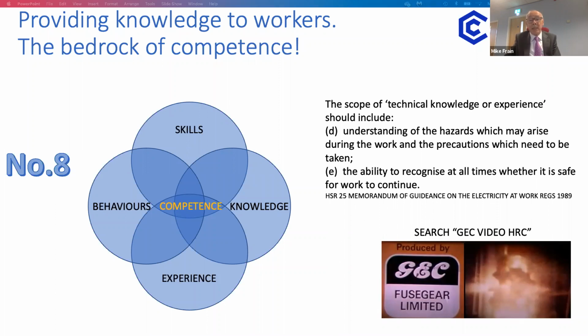Some may remember the old GEC educational video from the 1960s showing switchgear explosions and how BS88 fuses reduce damage to zero by disconnecting high fault currents very rapidly. It showed catastrophic damage from impressive explosions - I remember it well from my apprenticeship. Looking it up again, the prospective fault currents were at levels of 38,000 amps and 60,000 amps at low voltage, with fuse links disconnecting short circuits in less than half a second, because they operate within that safe, current-limiting zone I mentioned earlier.